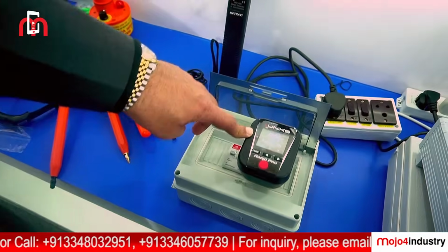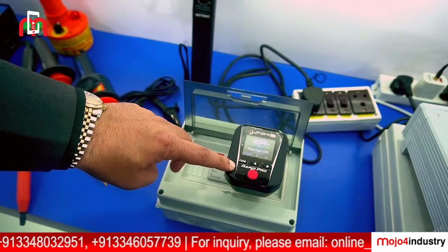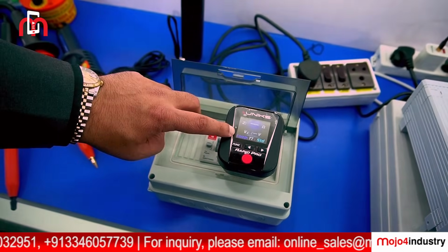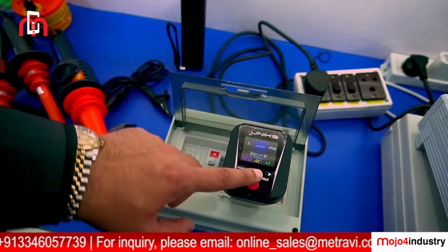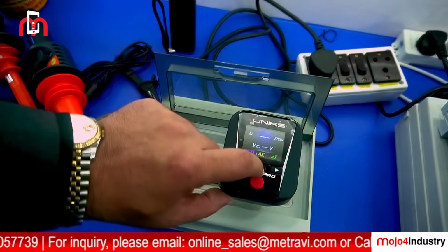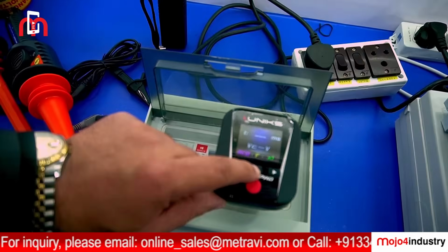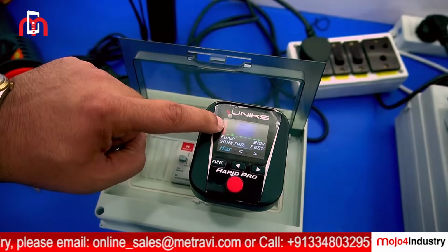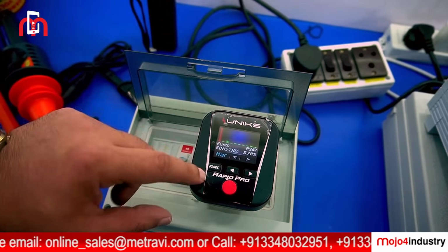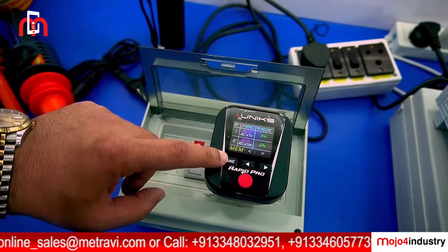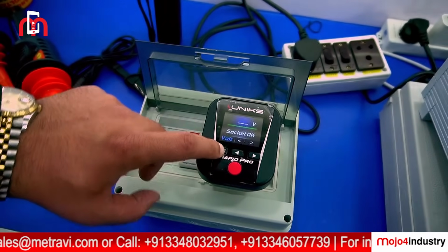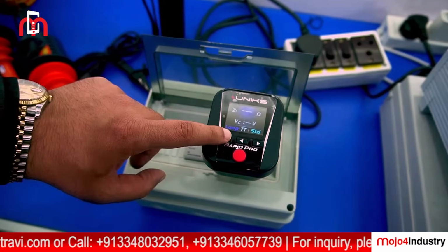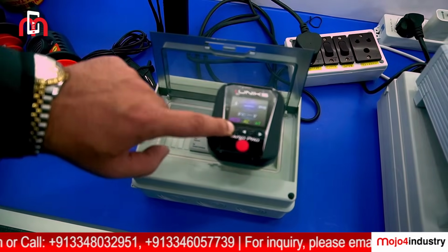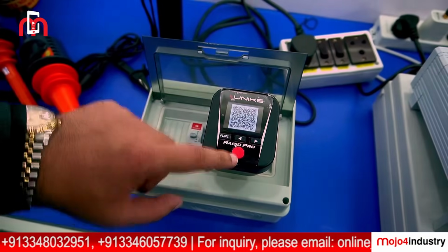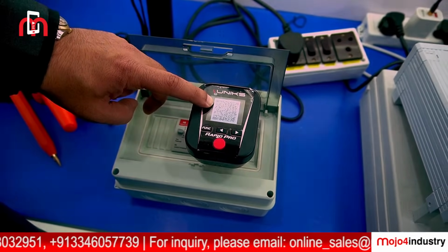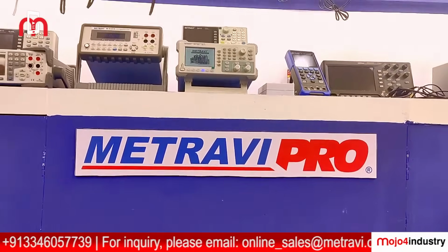This is another new instrument. This is called Rapid Pro. It is made in Italy. It measures the loop impedance for RCD, all kinds of RCDs. It measures the trip current and the voltage. It measures the voltage with all the harmonics. Individual harmonics are also displayed. It stores all the data here. And finally, when the testing is over, you can generate a QR code. Once you scan this, you will have a PDF report on your phone. These are 6.5-digit multimeters.